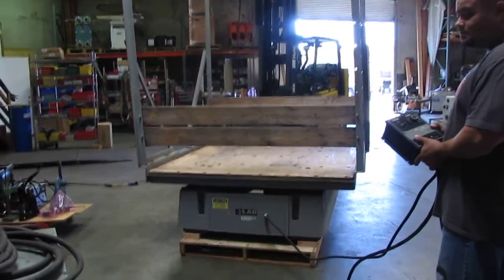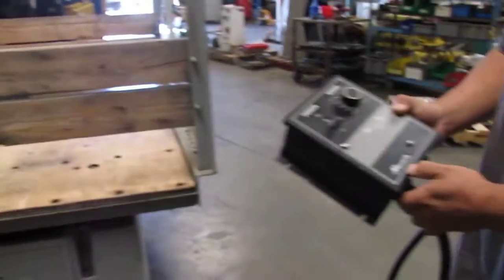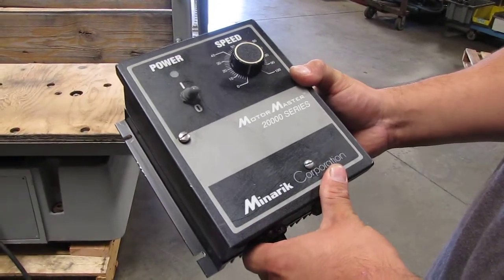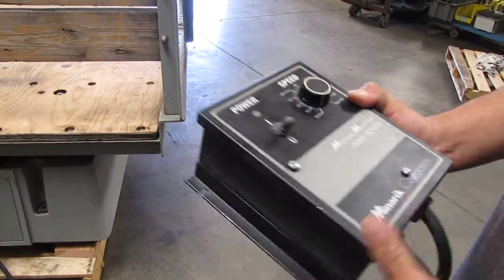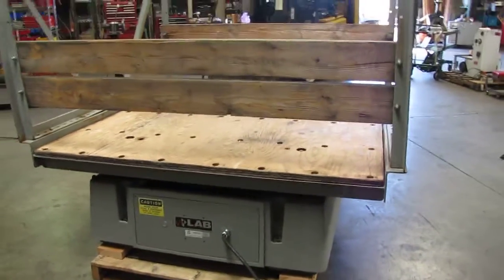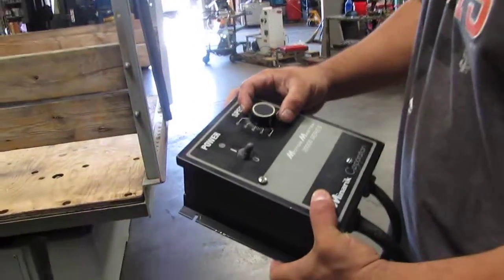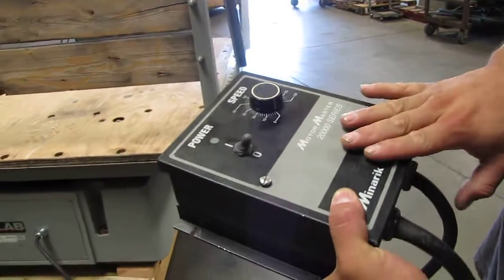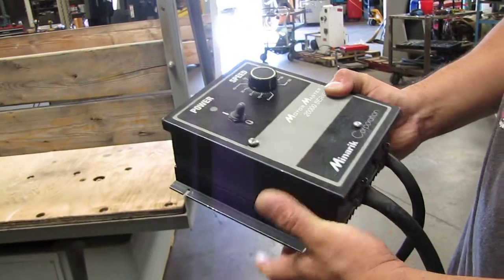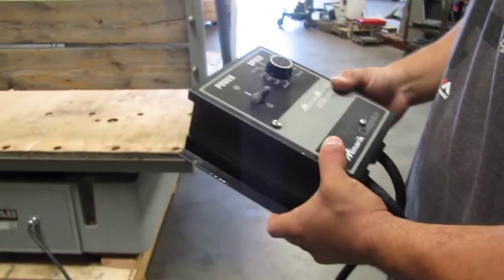Here we have a lab power shaker tester. We connected this unit to a Minarik. It's a DC 2000 series DC controller. The motor inside runs on 180 volt DC voltage. We're going to go ahead and test this unit and show you that it does work. This one hooks up to the power source, which is 230 volt single phase power, and then it converts it to DC and runs that DC motor inside.